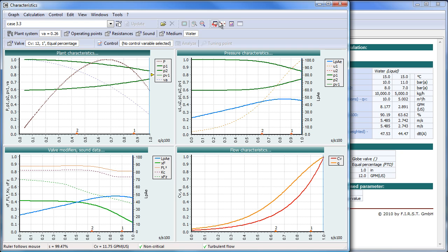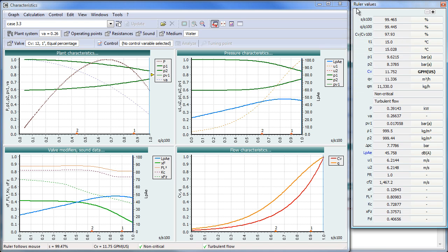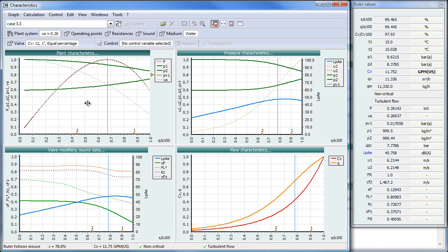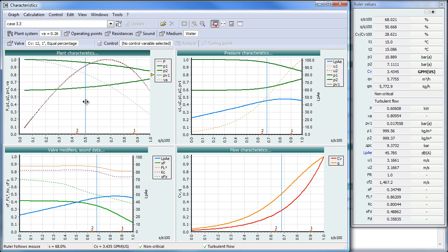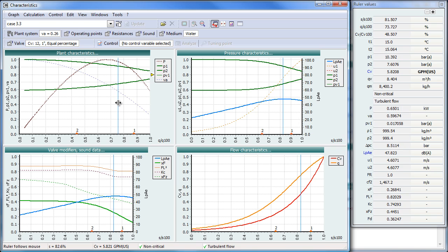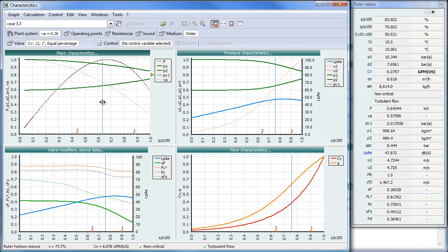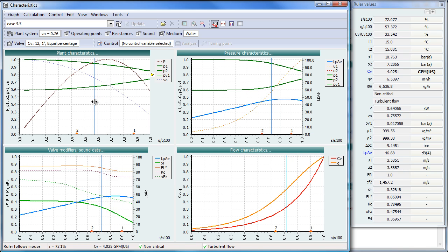This will pull up the graphics. We will add one more element, which is the ruler values. It brings up the ruler values. What is important is that we get four quadrants, which is the foundation of Conval. What's important is that you get a dynamic ruler — you can see that if I'm moving the cursor in the top left window, that window is in function of flow, and the other three quadrants are in function of travel. You see a dynamic ruler, and you can also see the ruler values on the right.